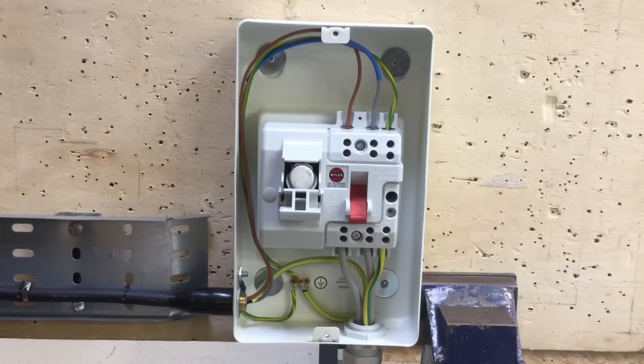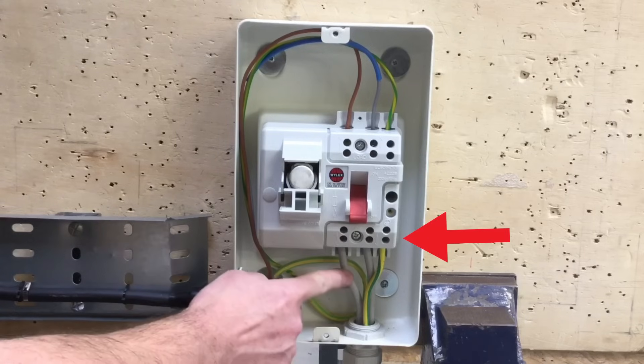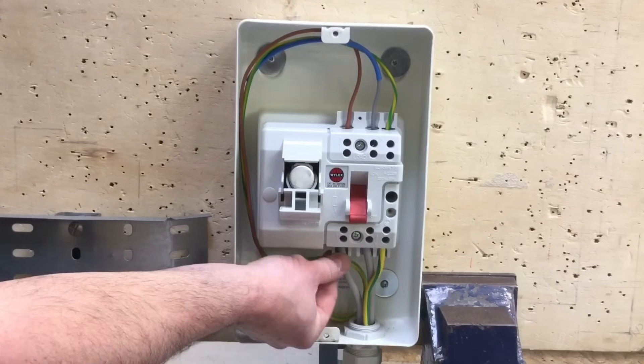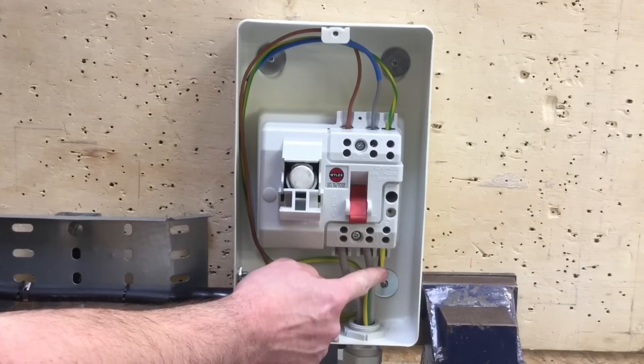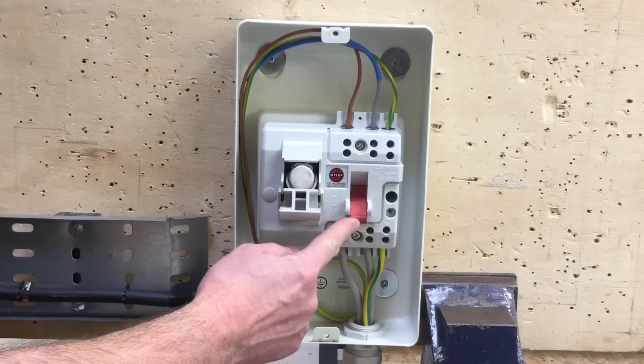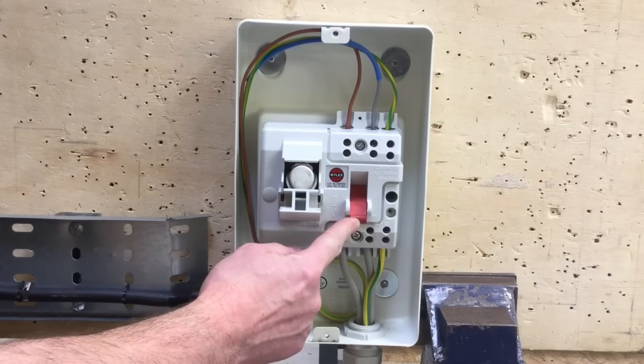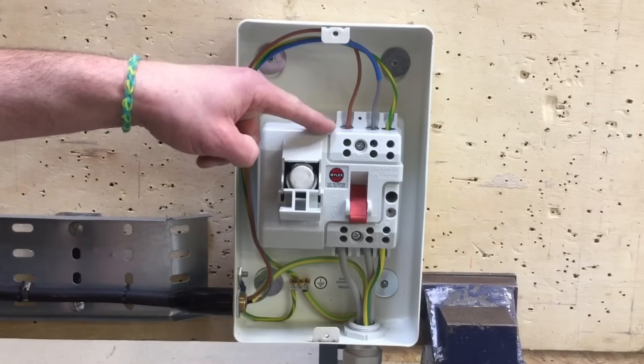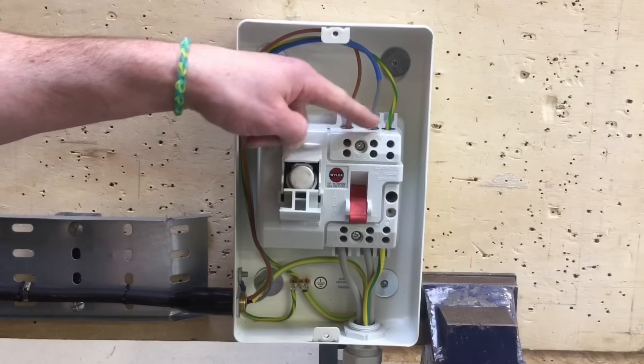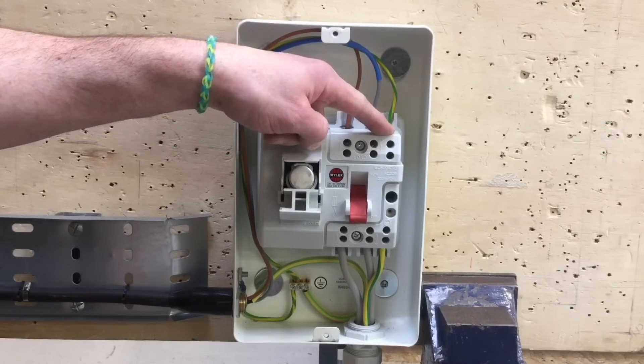Inside the Wylex switch disconnector fuse, the supply comes into the bottom of the isolator — in our case the tails — with line, neutral and earthing conductor coming in at the bottom. We have a double pole switch isolating both line and neutral when operated, and on the outgoing side we have the final circuit labelled 'load', with line, neutral and circuit protective conductor going out.